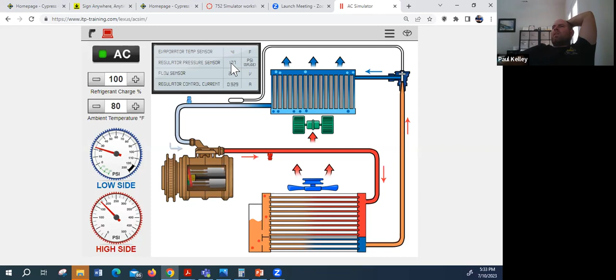And if you look right here, the regulator pressure sensor, this is actually going to be the refrigerant pressure, and that's probably going to be on the high side. So 177 on the high side, does that align with the high side gauge? Yeah, that sensor's probably good.